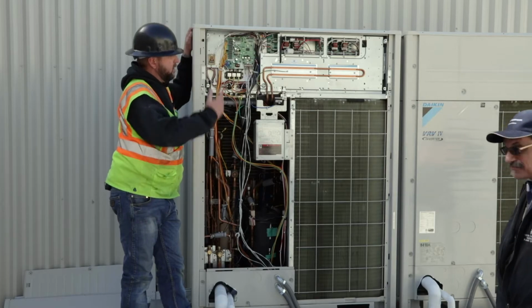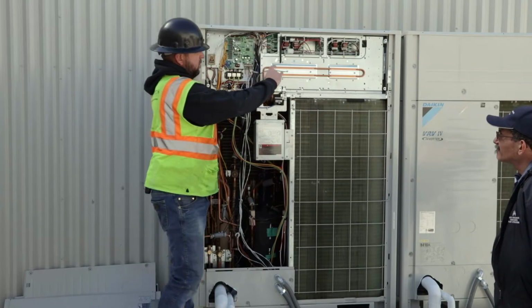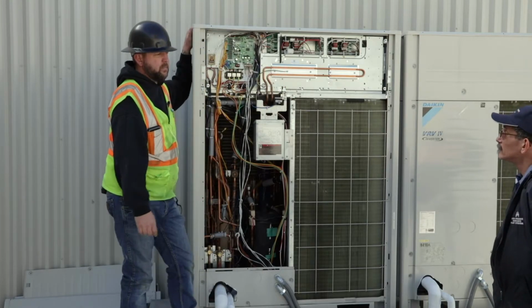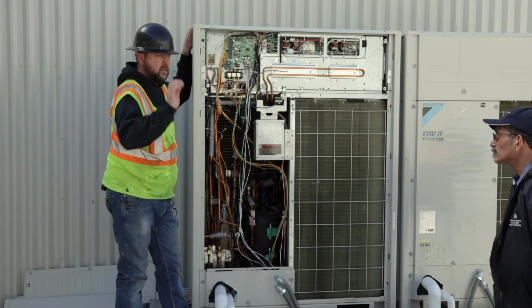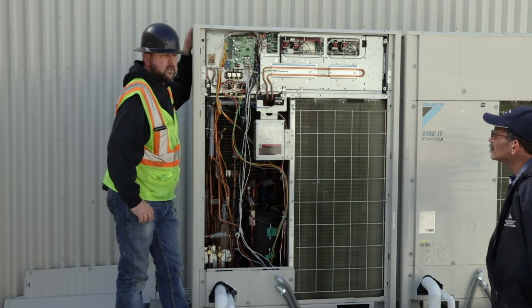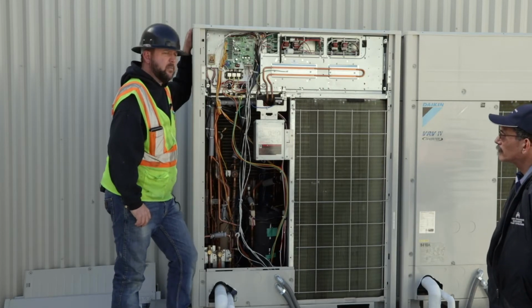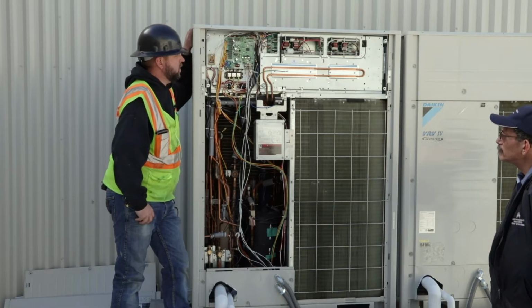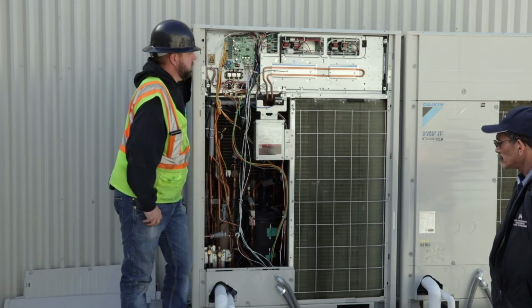If it's a condenser fan motor, inverter board, any of that, because I have had these inverter boards go out, and it was on a new project, and it happened when they're doing generator testing. They're kicking that generator on and off, and took out these inverter boards. I actually had Daikin come out, and that's the only thing that they could come up with, those spikes. But they're not too hard to change out.